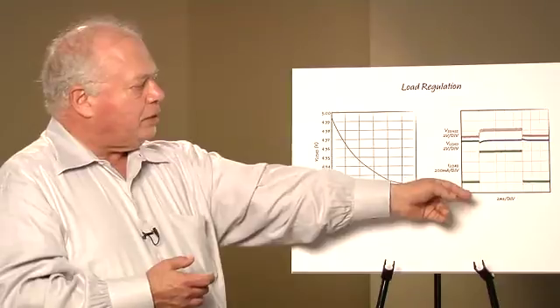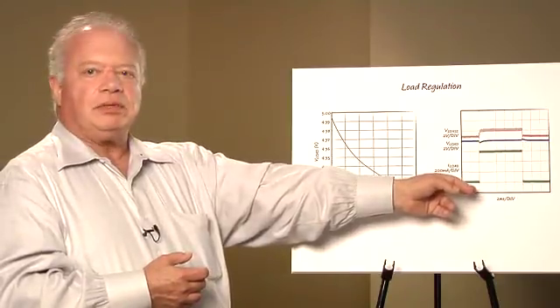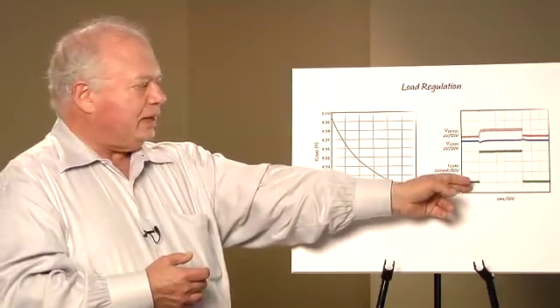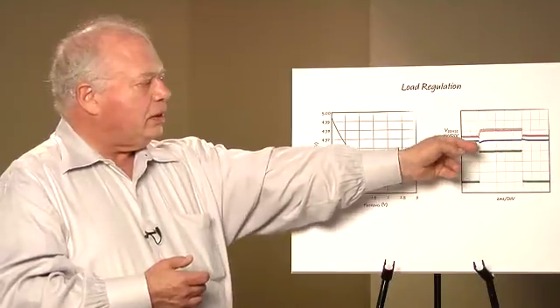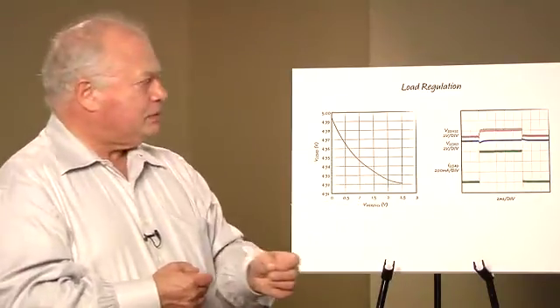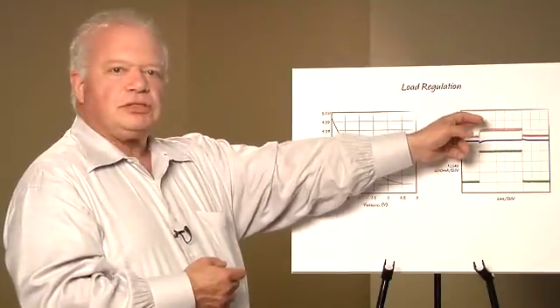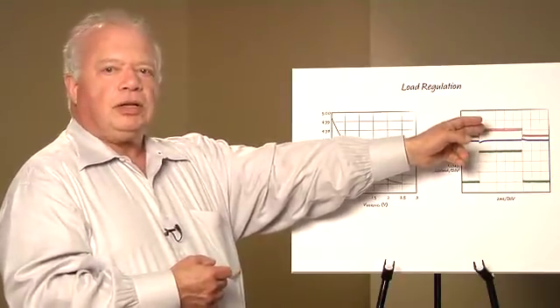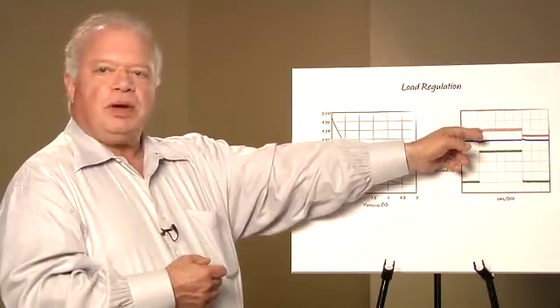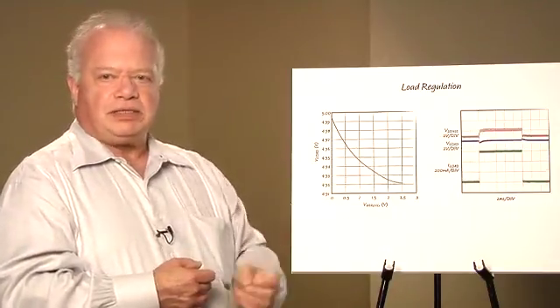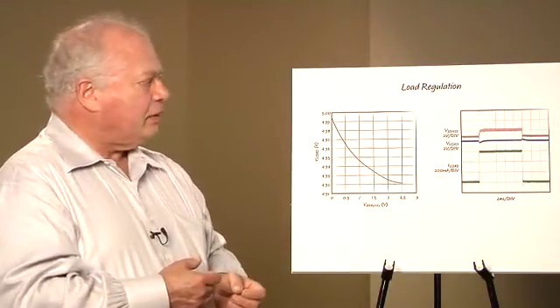Here's a scope photo of what the output looks like on the 4180. This is my load current, jumps up to 600 milliamps. This is the output of the supply, and that jump is the correction voltage due to the line drop. The fuzz on this waveform is the interrogation signal, and this is running at about 8 kilohertz.